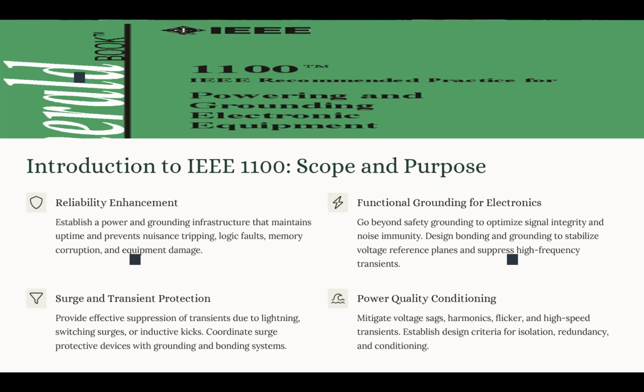Now, as we said, traditional grounding was mostly focused on safety, okay? So it was to clear the faults and protect the people. IEEE 1100 introduced functional grounding in addition to that safety grounding, which basically creates a stable, low impedance reference plane for our signal circuits. Now, we mentioned some of the key functions of the framework and the recommendations in IEEE 1100. Let's go into those.